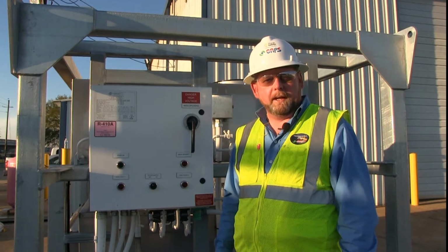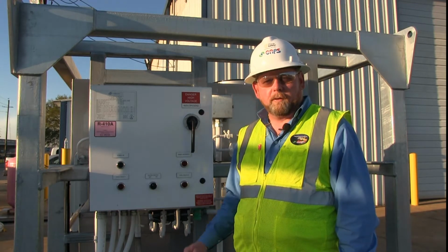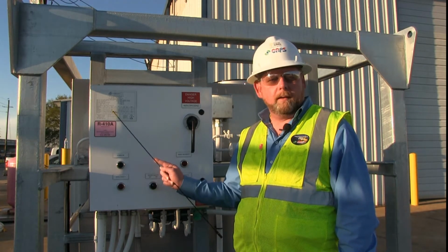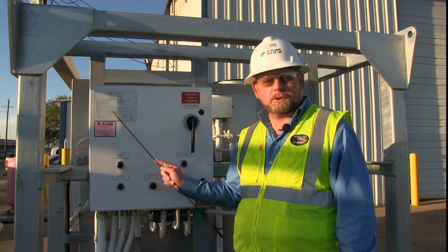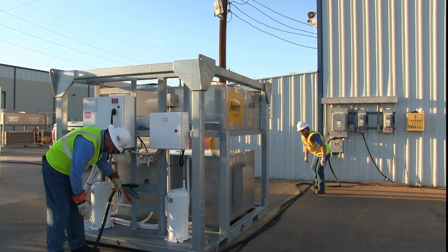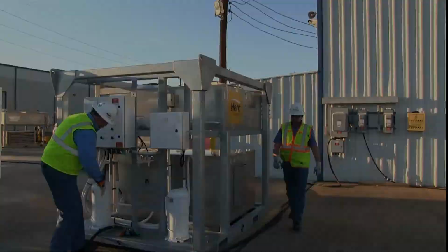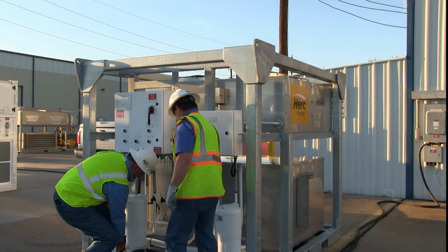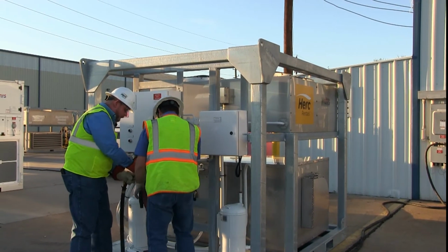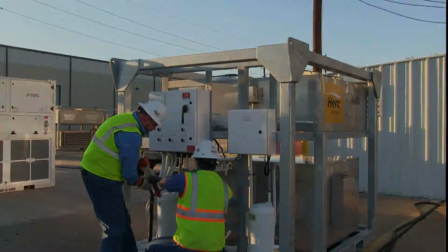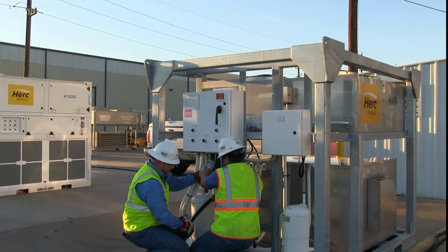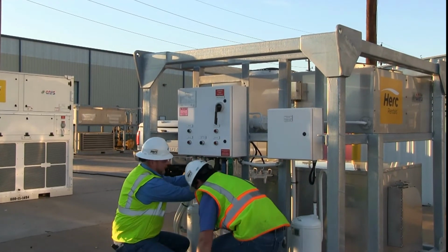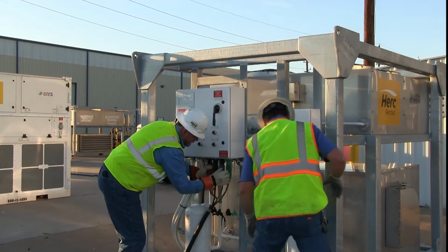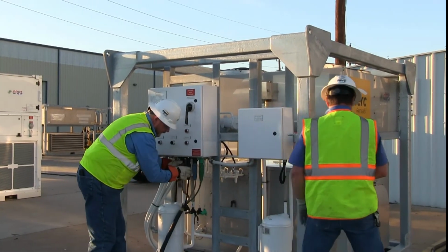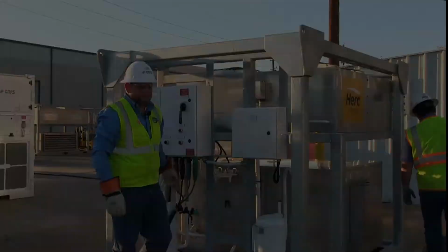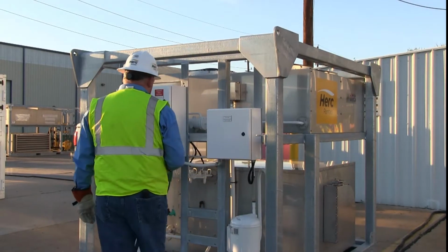Now that the unit's been placed in position, you want to first verify the required power to operate the machine. You bring the cable over to the connection point, then we're going to start hooking up the power. You always hook the ground lead up first. Okay, now that we've got our power hooked up, we're going to go remove our lockout tagout clip and verify phase rotation. Okay, we've energized the unit now.